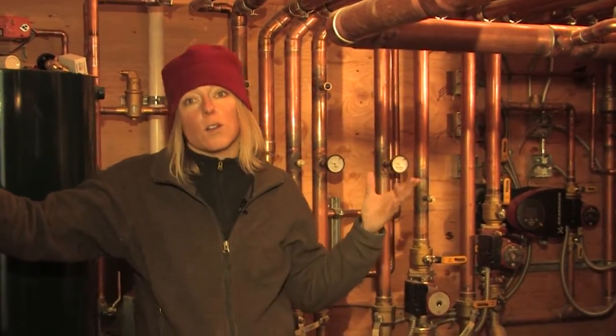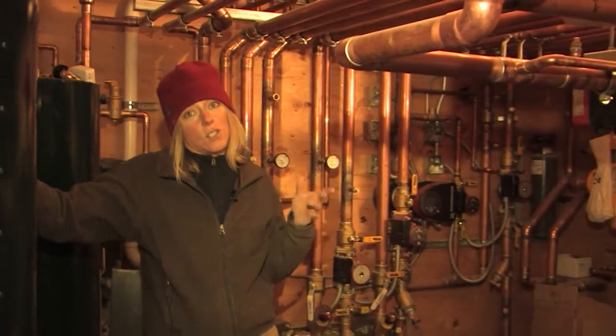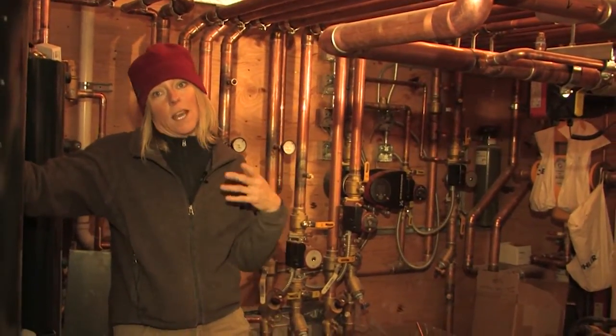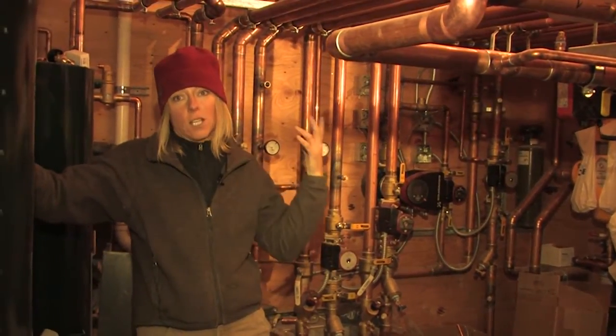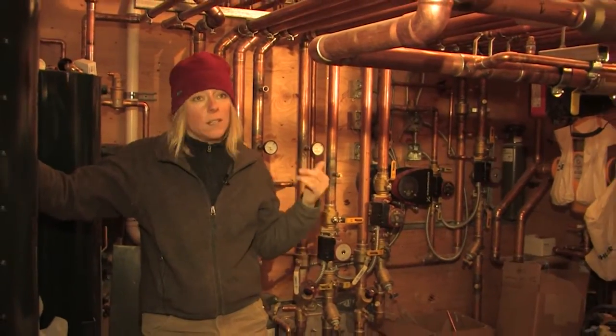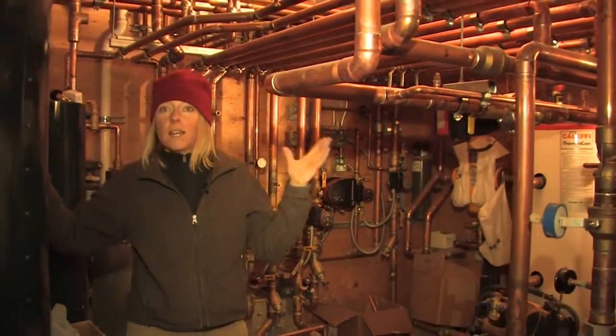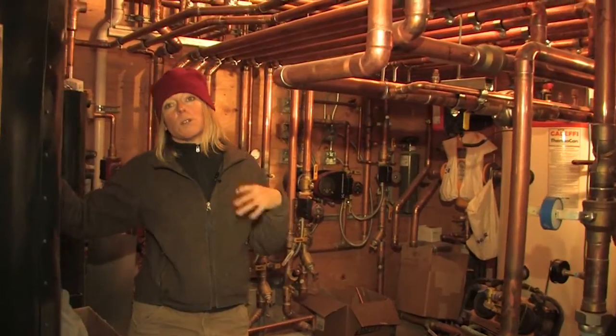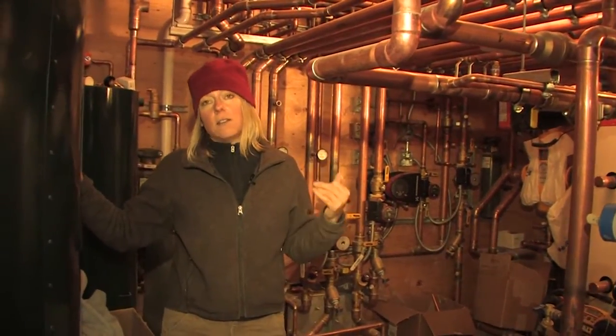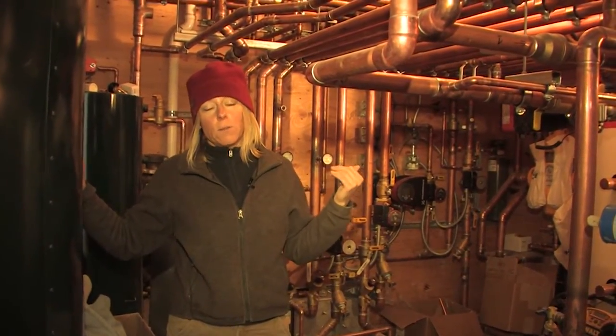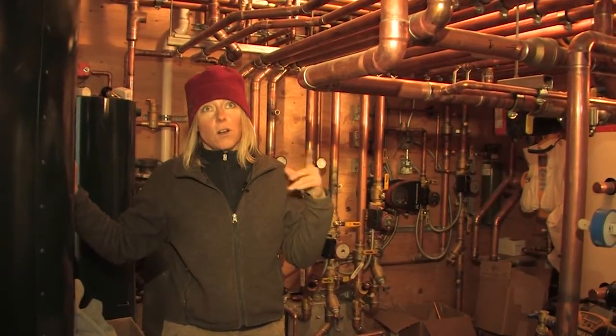So that hot water will go through the heat exchangers into the hot tank, and we'll use the energy captured off of them to preheat the mash tun, and to heat and cool the building. What we're left with is cold water, which we can use for cooling the condenser again, cooling down the mash and the fermenters, and also for our air conditioning system.